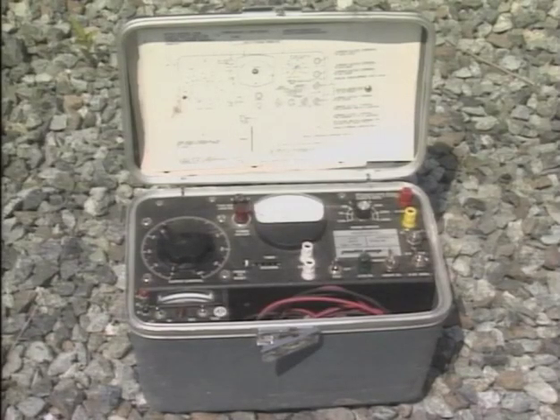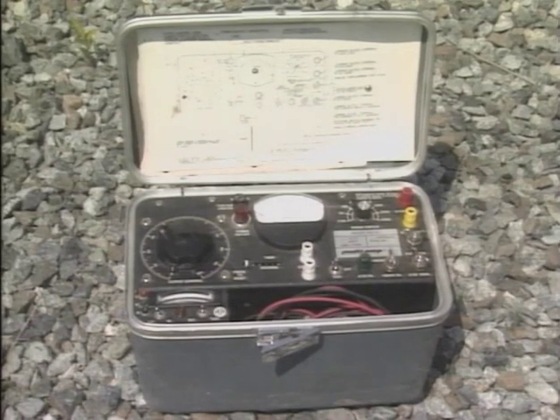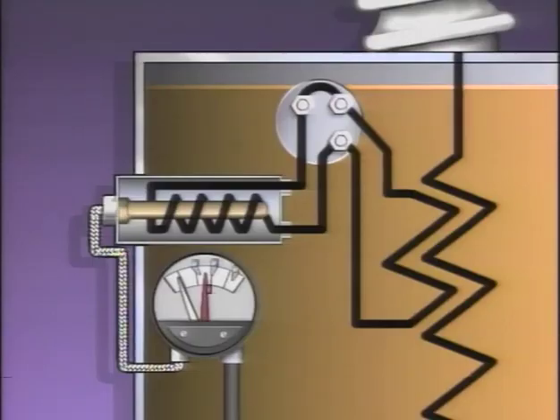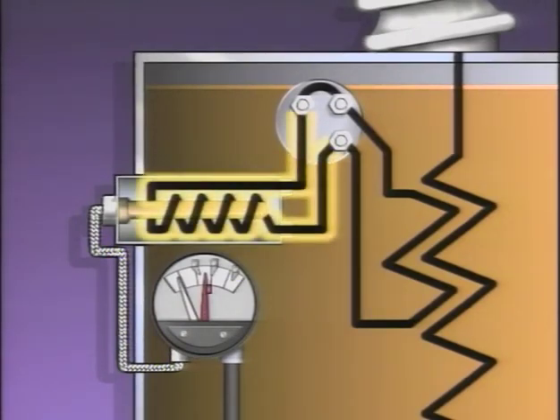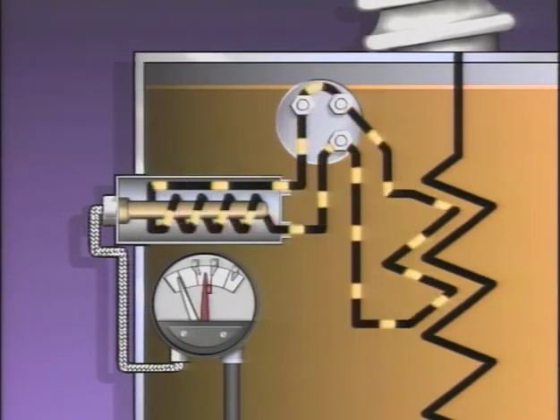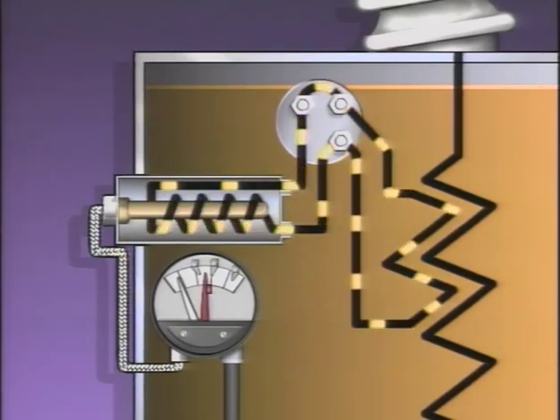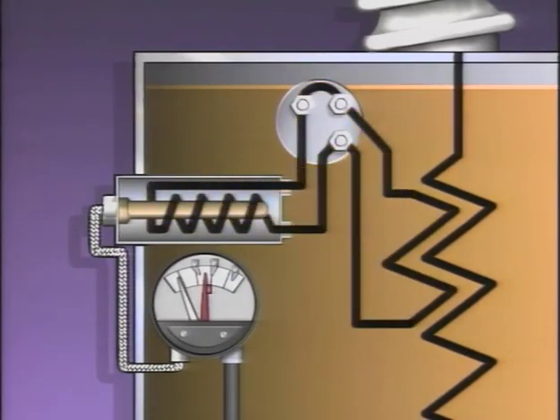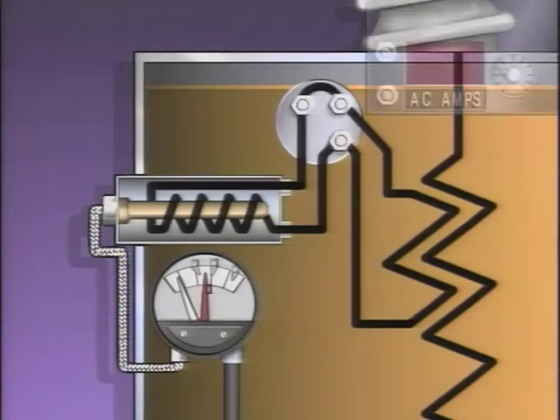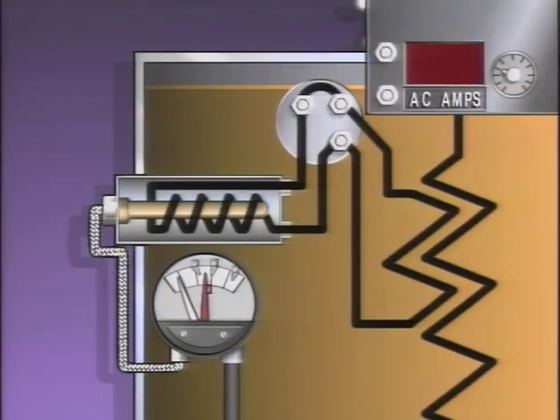The equipment needed to test a heater circuit includes a variable current source unit with an ammeter, used to apply current to the heater circuit. To perform the test, a constant current must be applied to the heater circuit for about 30 minutes. The current transformer in the system is already applying current to the heater circuit, but the current varies with the load on the power transformer. So for the test, the current transformer will be removed from the circuit and a current source unit connected in its place.